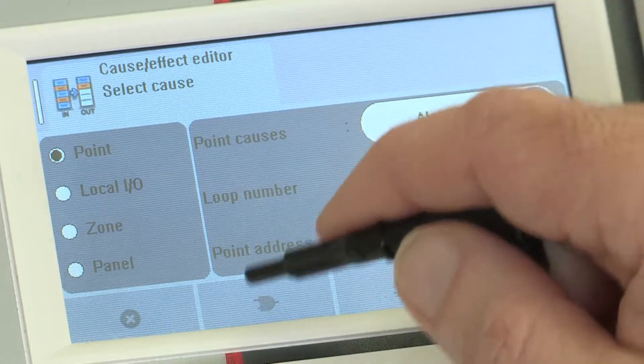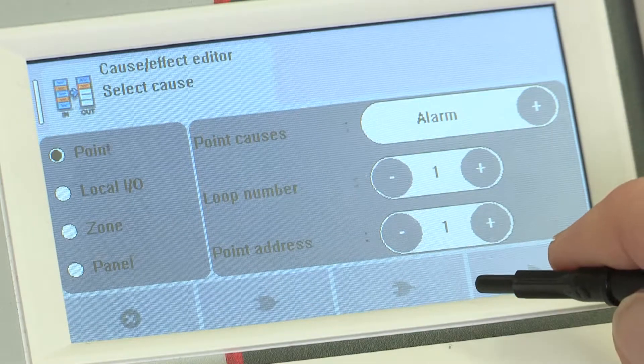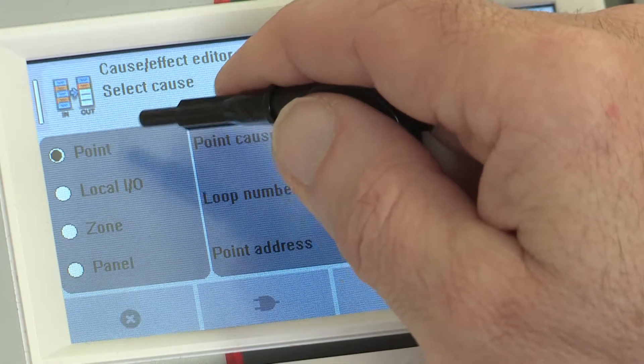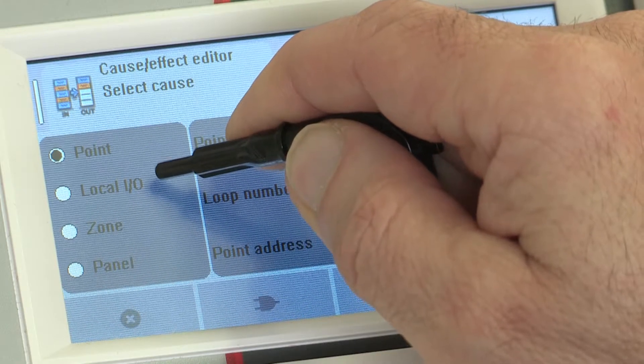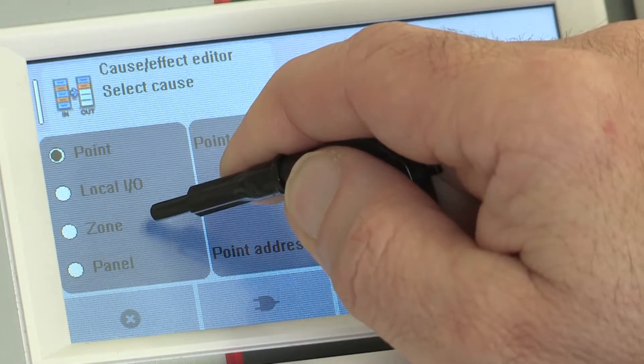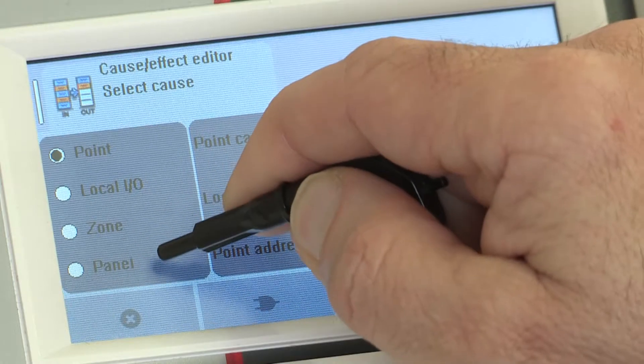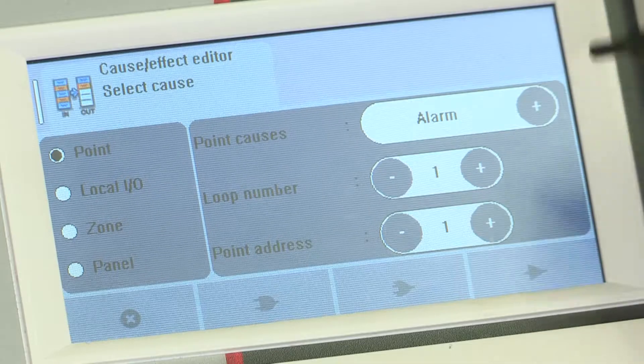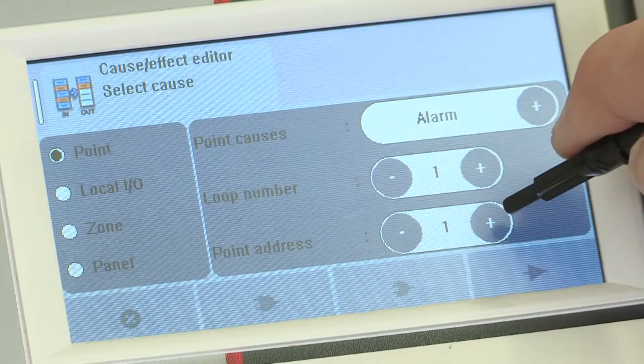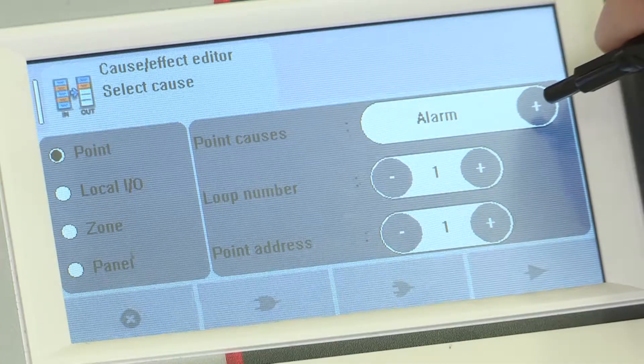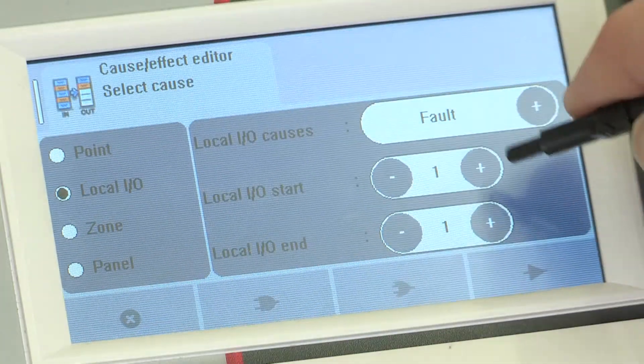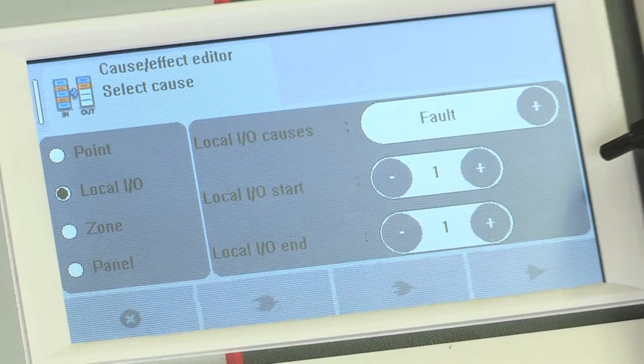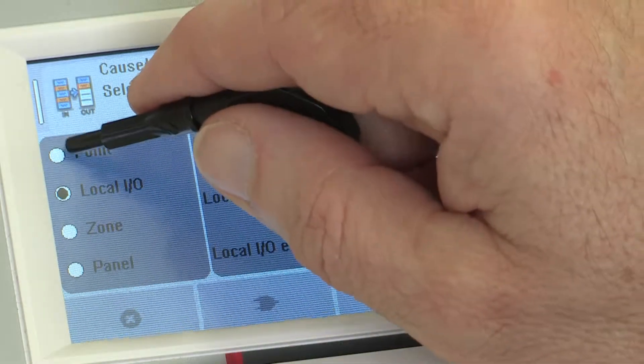The first screen is used to define the cause. This can be a single point device, a local IO, panel input, a zone, or the whole panel. If point is selected, you can select the address. For multiple zones, you can select the first and last zone ID. Once you have chosen which input device or group, you can select the point cause itself.